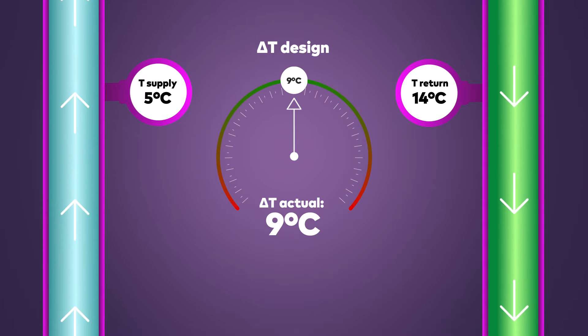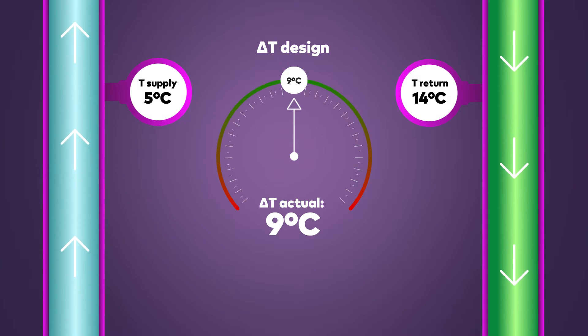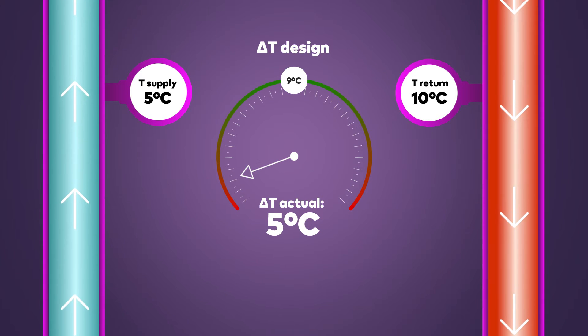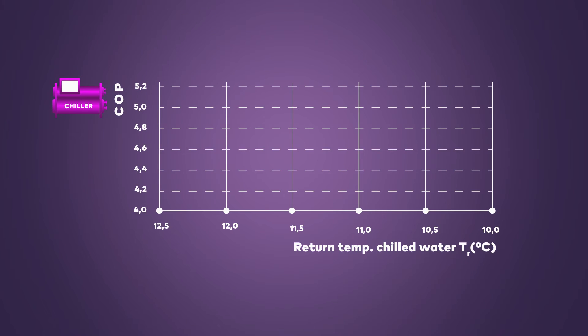In an efficiently functioning HVAC system, maintaining the system-designed Delta-T and power output indicates effective heat transfer at the design flow rate, ensuring that the system is running at its optimal performance. However, a lower Delta-T than the one specified in the design indicates lower efficiency. A two-degree reduction of the return temperature of the chilled water can lead to a drop of up to 15% in the coefficient of performance of the chiller.